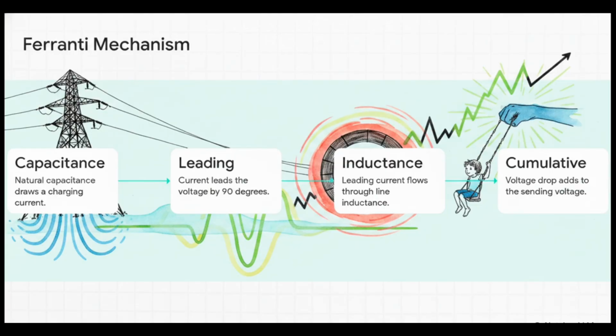Well, let's walk through the chain reaction. Step 1. Every transmission line has this natural distributed capacitance between its conductors and the ground below it. When the line has no real power load at the end, this capacitance naturally draws what we call a charging current. Step 2. Because this current is capacitive, it leads the voltage by exactly 90 degrees. Step 3. As this leading current flows down the wire, it passes through the line's distributed inductance. And Step 4. This creates a voltage drop that is perfectly in phase with the sending end voltage.